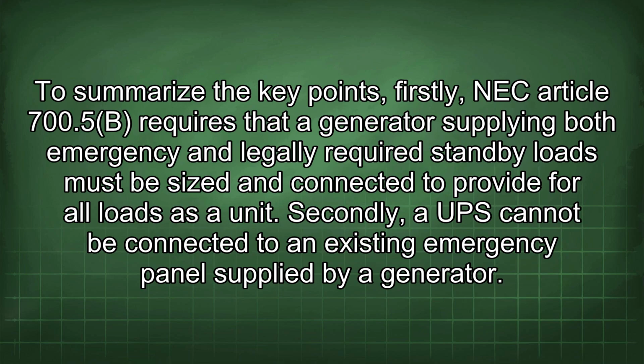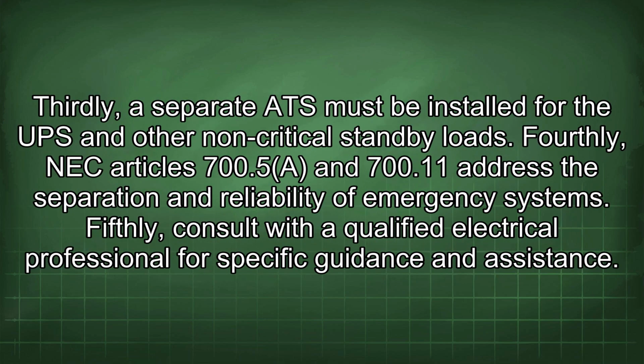To summarize the key points, firstly, NEC Article 700.5b requires that a generator supplying both emergency and legally required standby loads must be sized and connected to provide for all loads as a unit. Secondly, a UPS cannot be connected to an existing emergency panel supplied by a generator. Thirdly, a separate ATS must be installed for the UPS and other non-critical standby loads. Fourthly, NEC Article 700.5 and 700.11 address the separation and reliability of emergency systems.